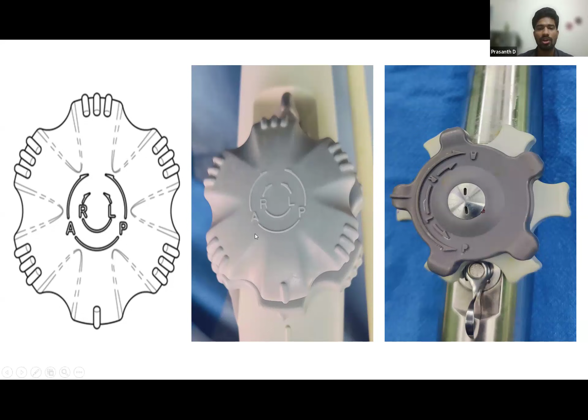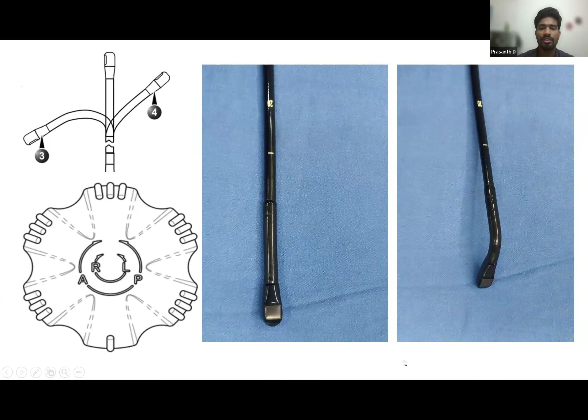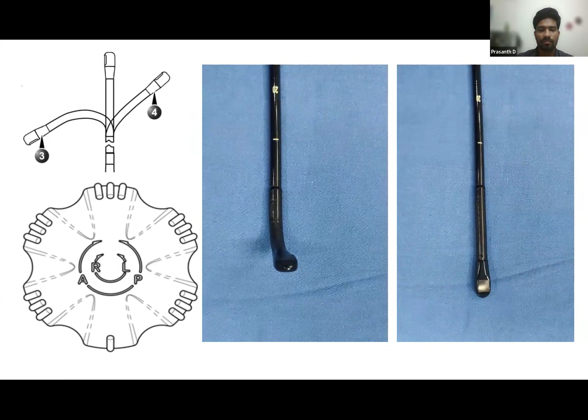So as we can see, clockwise rotation produces anteflexion, and counterclockwise rotation moves the probe tip to the retroflexion position. The outer wheel, if you rotate clockwise, the probe tip will be flexed to the right side, and if you rotate counterclockwise, it will flex to the left side.